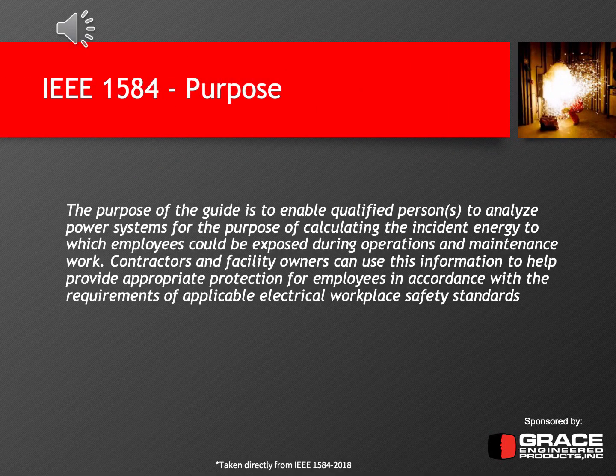So before we get into the background and some of the meat of this presentation, the first thing I wanted to cover was the purpose of IEEE 1584. They have a purpose statement in the document, which is on the slide word for word, that says it is to enable qualified persons to analyze power systems for the purpose of calculating the incident energy to which employees or workers could be exposed during operations or maintenance work on electrical equipment, particularly energized electrical equipment. So contractors and facility owners can use this information to provide appropriate protection for employees. What this means is they take the results of the arc flash analysis, and you can then reference other standards such as NFPA 70E and determine what the appropriate level of personal protective equipment, or PPE, is for someone performing energized work while doing maintenance or operations work on electrical equipment.